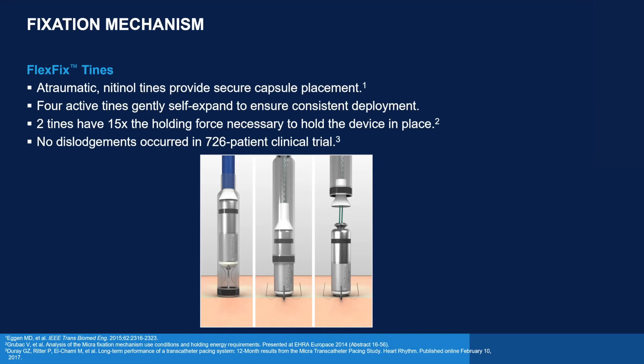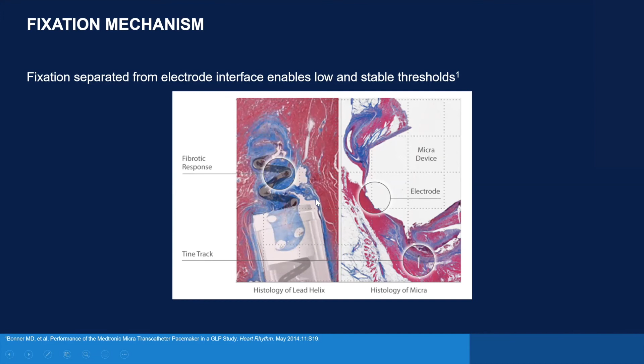This is some of the histology that also shows why this device works quite well and has a very low pacing threshold, because the tines are non-reactive and basically grip trabeculated muscle rather than going into the muscle as a traditional active pacemaker lead does with a screw. There is no fibrous tissue, this blue stuff is fibrous tissue around a traditional pacing lead. You don't get that with the tines, and hence the threshold, that is the amount of energy required to stimulate the heart, remains fairly consistent over time. And this effect of fibrosis doesn't affect the battery longevity.